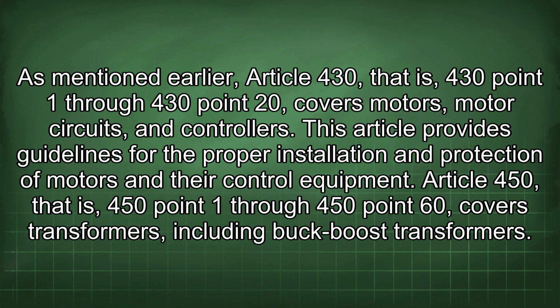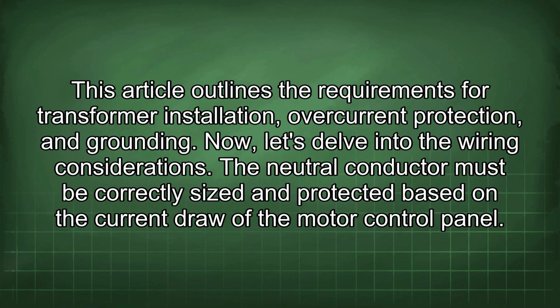As mentioned earlier, Article 430, that is 430.1 through 430.20, covers motors, motor circuits, and controllers. This article provides guidelines for the proper installation and protection of motors and their control equipment. Article 450, that is, 450.1 through 450.60, covers transformers, including buck-boost transformers. This article outlines the requirements for transformer installation, overcurrent protection, and grounding.